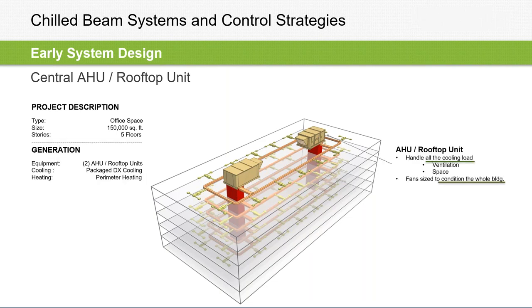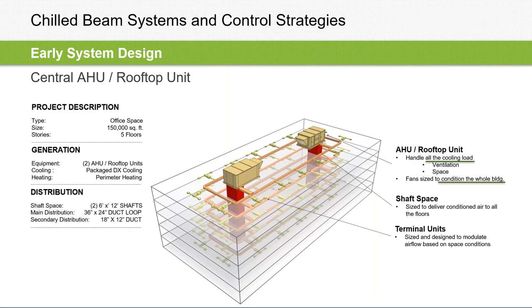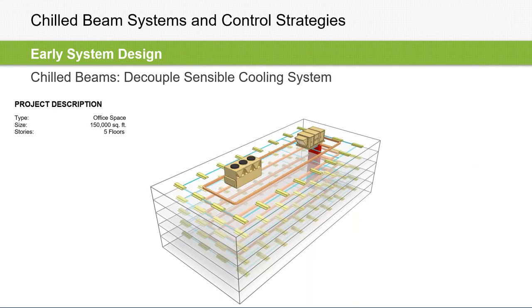But what that means for the building is that you would go from these two risers in this VAV style design, you've got a ring around the sides as well, but you have two main air handlers with pretty large risers. And when we move this to a chilled beam system, we're able to reduce the number of risers first to one. We can cut one of those out, and we also reduce the size of this riser as well. We're basically cutting out 60% of the CFM that you need, maybe 70 or at times 80%.